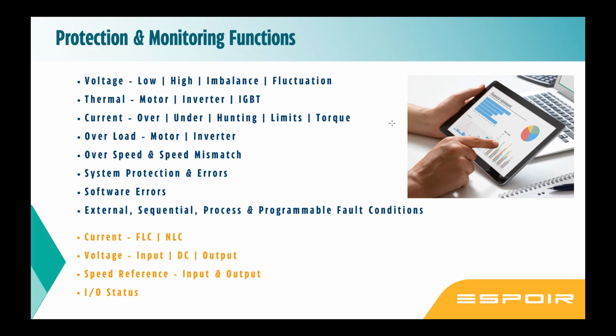Not every drive will give all the features. Undercurrent trip is required in many pump applications. We need to enable this aspect because if a pump is running dry, where the pump is running but water is not coming, the pump will burn within 20 minutes. So the undercurrent trip is to be tuned in such applications. I'm giving certain examples. This is a very, very vast industry. Within 1 hour, covering all the aspects is a task. So I'm just trying to give a glimpse of what is what.